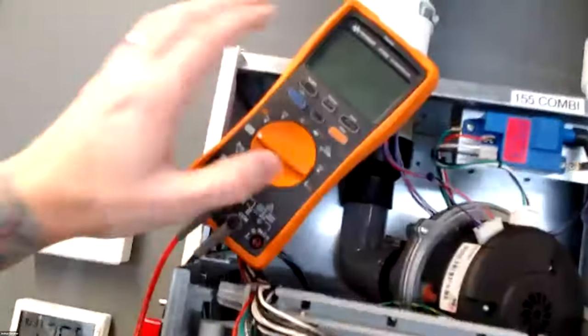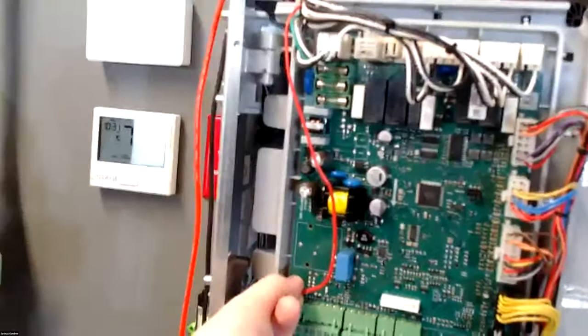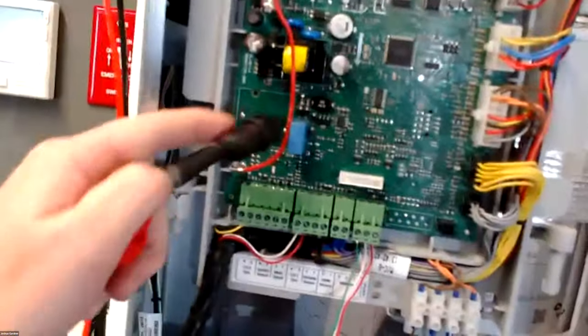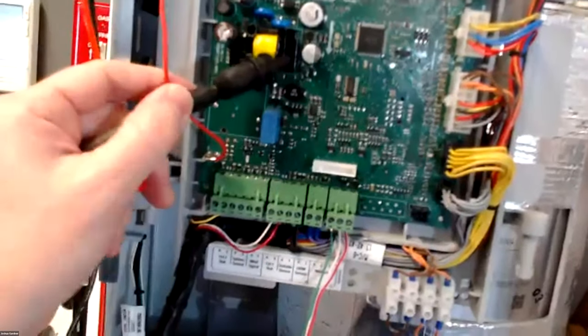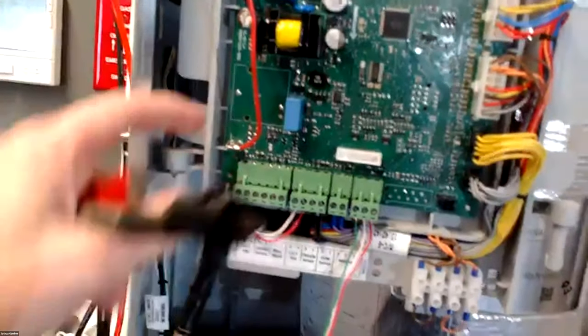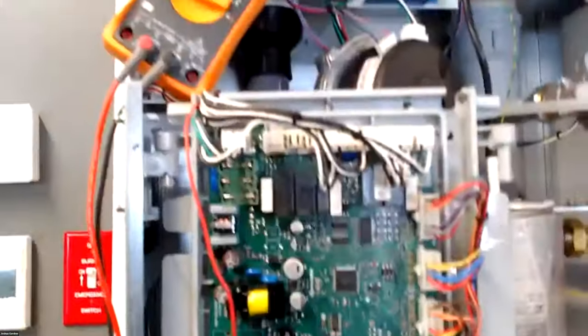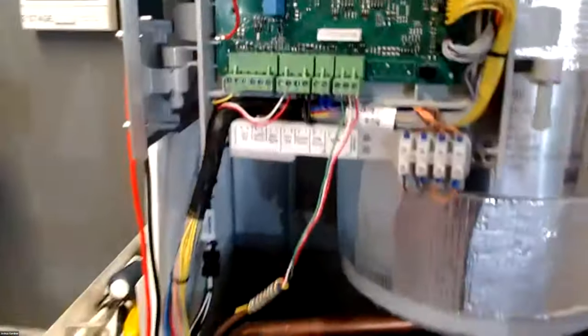It doesn't show it in tenths. So if you're really trying to do some troubleshooting, it might be better to get your meter out and run it in series with this. So you pull this lead off and you'll take your meter, clamp one lead onto the red wire and the other lead onto the spade connector on the board. And you'll run this in series through your multimeter to get your microamp signal. And this will give you a little bit more precise signal.